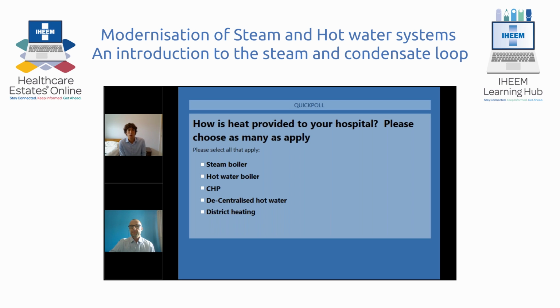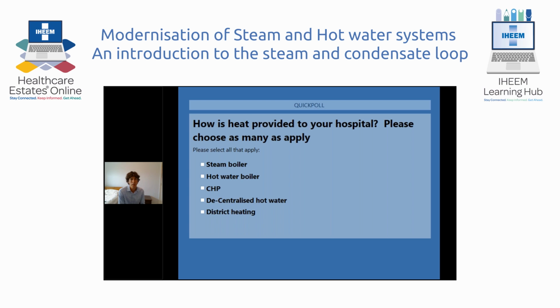Thanks, Gunther. While we're waiting for those results to come in, I'll talk you through the boiler heat losses. Typically in hospitals, we're using fire tube boilers. This is where we combust the natural gas in a burner, and it flows through a series of tubes in a water bath with the steam evaporating off the top of the boiler. This type of design can use many different types of fuel, including biomass if required.